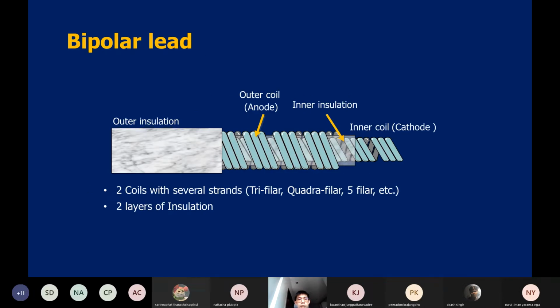The bipolar lead is different. There are two coils with several strands inside the lead and two layers of insulator. The tip of the bipolar lead is the cathode, and the layer outside in the lead is the anode. So with this bipolar lead, you don't need to use the pulse generator as the anode.